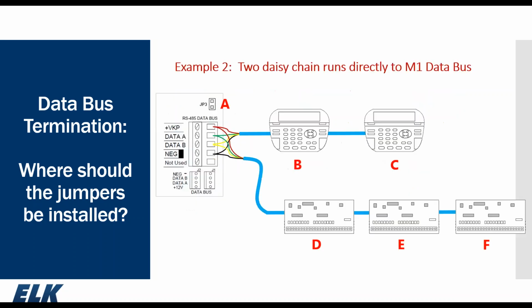The next example we have is 2 daisy chains off the M1. This is using just regular 4 conductor. So the top one is our 2 keypads. The bottom one is, we'll say these are input expanders we've daisy chained together. In this case, the M1 is in the middle. We have our 2 home runs. The last device on each home run would have the terminating jumper installed. Overall, added up, the total length of both of these should not exceed 4,000 feet.